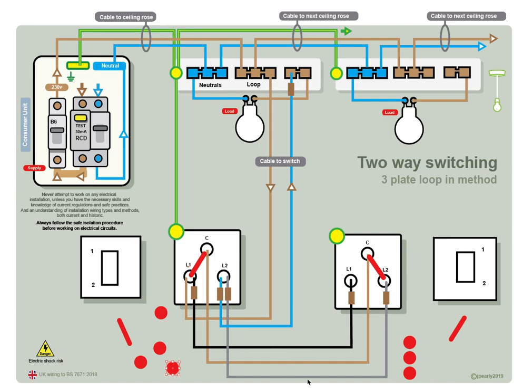Then you have your three-core and earth cable, three-core CPC. These are known as your strappers. In this case we have black from L1 to L1, brown going from common to common, and L2 we've got gray going from L2 to L2. So L1 to L1, common to common to the two. Switch live, permanent live to L1, switch return to L2. You wire it like that, you're never going to have any problems with your two-way switching, it's going to work.